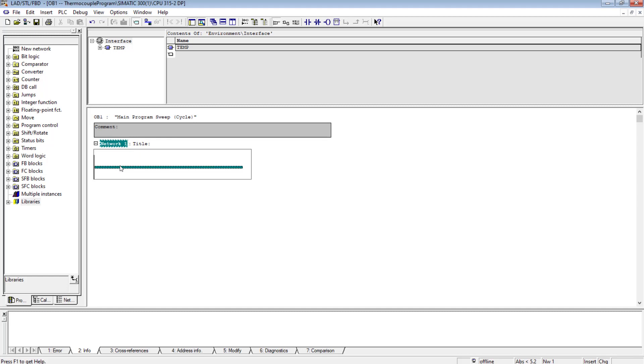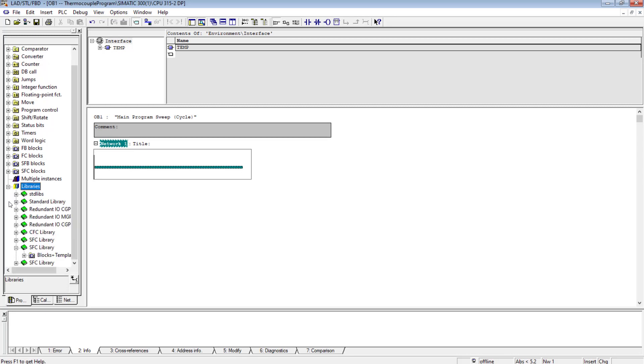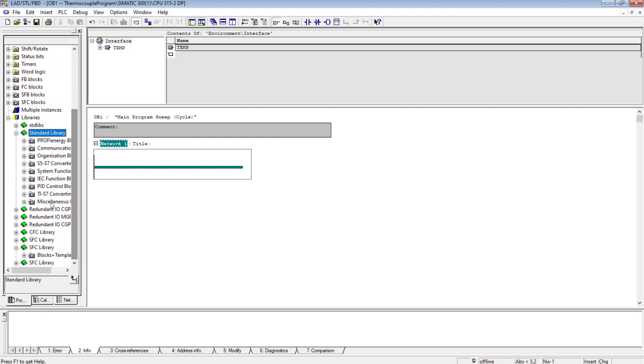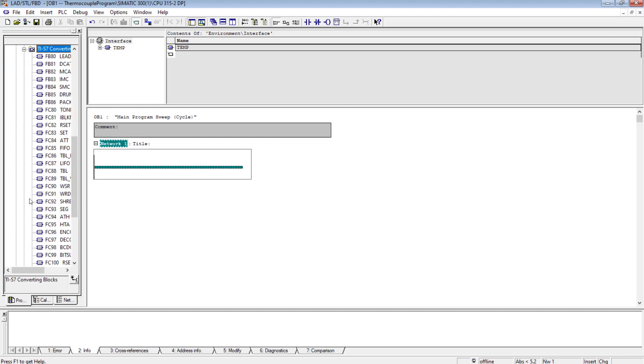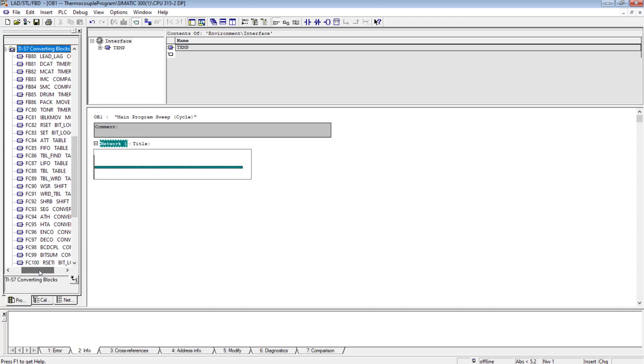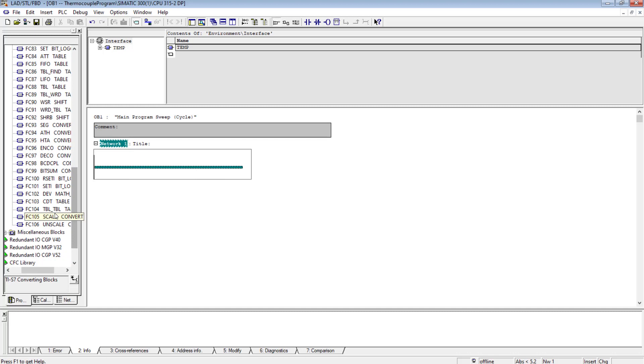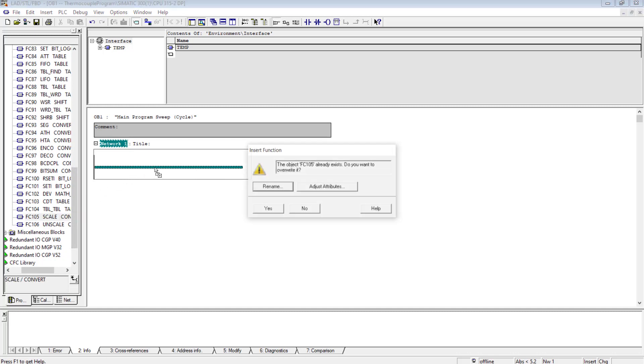Now I will be using the Scale function, the FC105 Scale function for the scaling of the thermocouple value. I will go to the library and in the standard library I have to go to TI-S7, S7 Converting section, and over here I will find FC105 Scale Convert. I will import it.